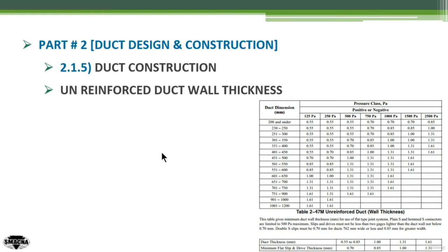To enter this table, you need two inputs: input number one is the duct dimension, and input number two is the pressure classification. The duct dimension represents the row, which you will intersect with the vertical column representing the pressure classification.